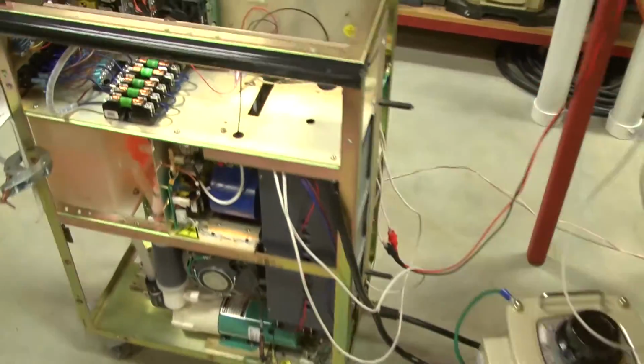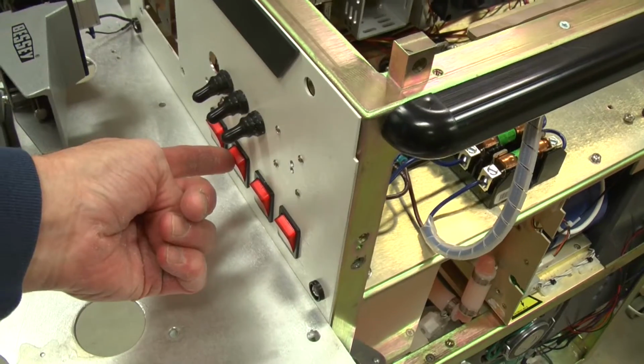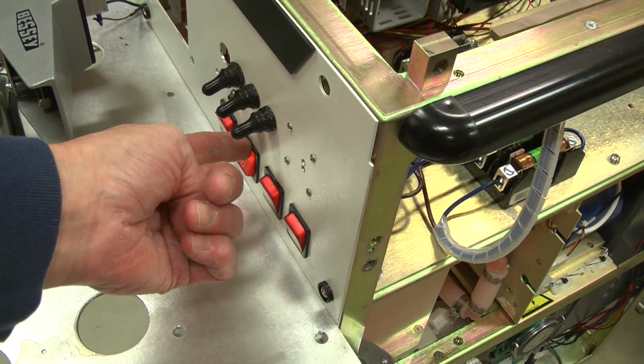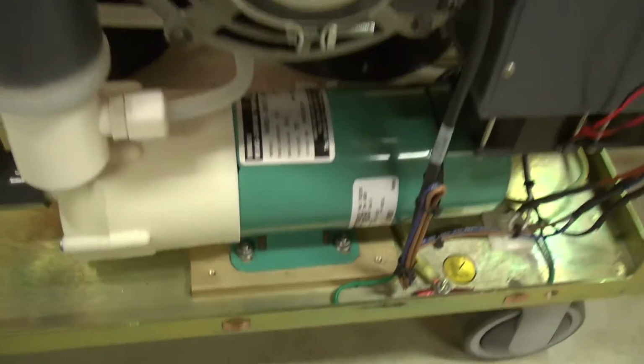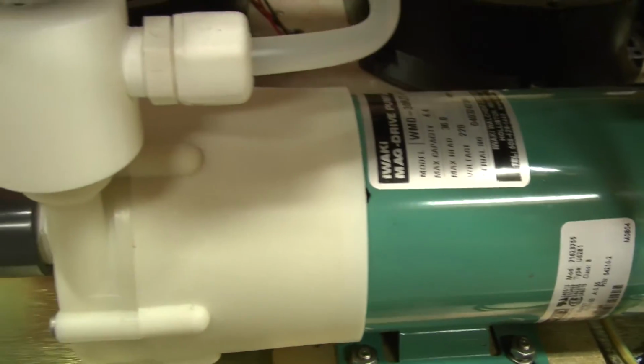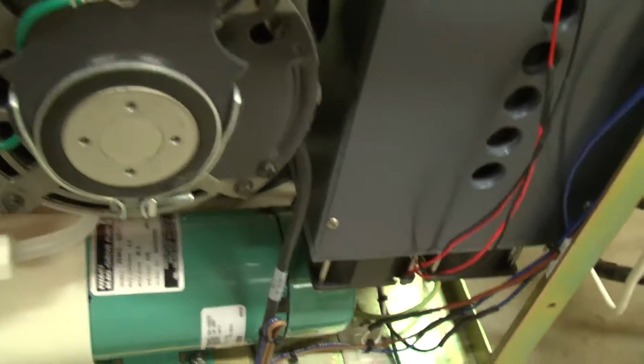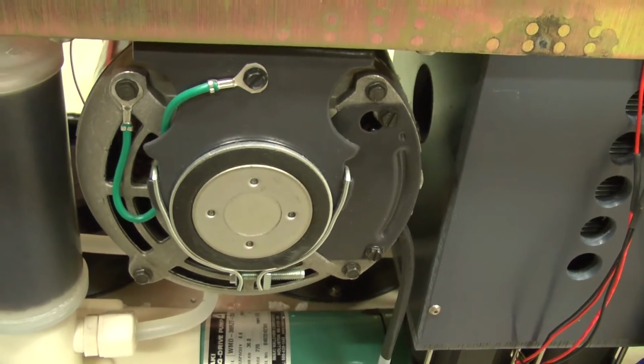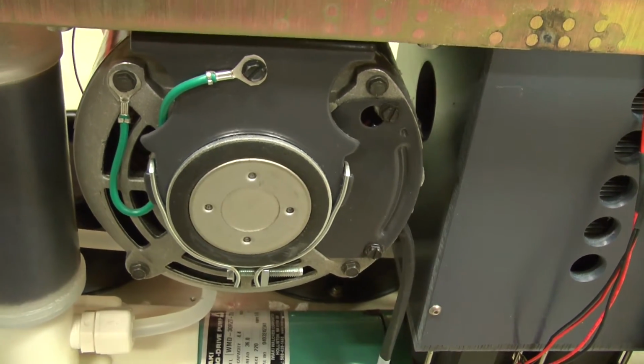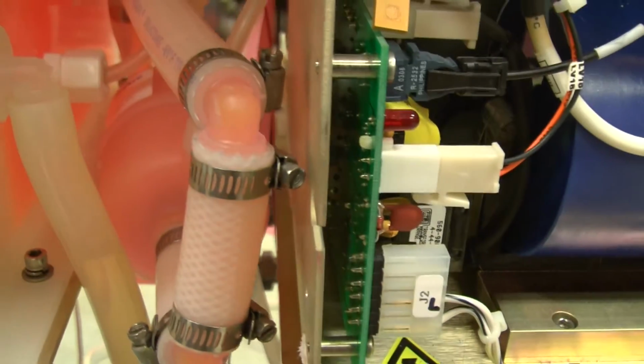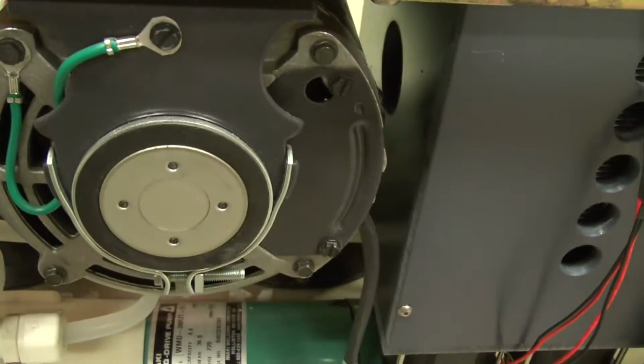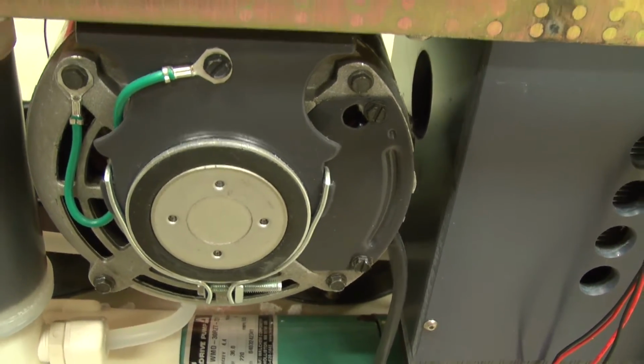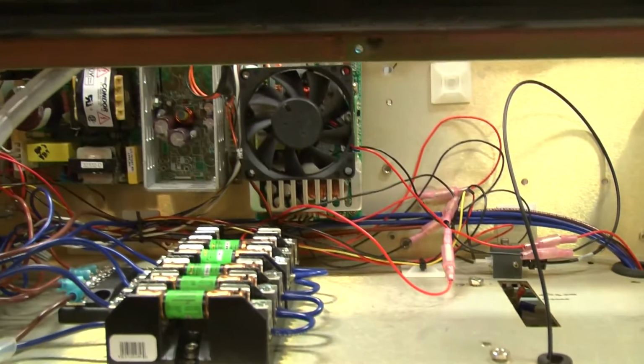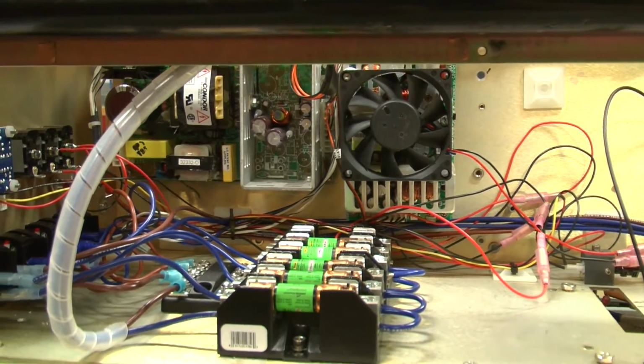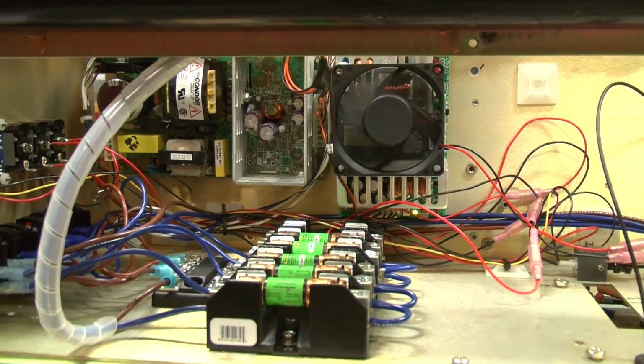And first switch I'm going to turn on is, I believe, the quiet pump. You can barely hear anything, but this is the small Iwaki pump that's pumping the DI water and cooling off the flash lamps. I'm now going to turn on the much louder Procon pump that pumps the dye. You can even see this little tube moves a little bit because it's under much higher pressure. I'm now going to turn on the 12-volt supply that actually allows the trigger transformer to operate and some of the other electronics and the cooling fans.